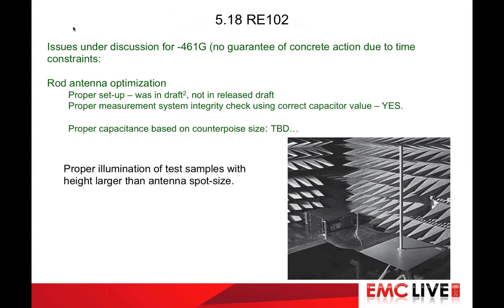Now, moving on to RE102. There were 3 changes discussed for RE102, one of which appears in the draft for industry review. There is a strong desire to either replace or at least augment the 461F rod antenna setup with one not requiring grounding of the coaxial transmission line directly below the rod antenna base. Because many test facilities don't have a low impedance ground connection at convenient locations. Also, a fully isolated rod antenna and counterpoise is desirable from an accuracy standpoint. This is not in the draft for industry review.